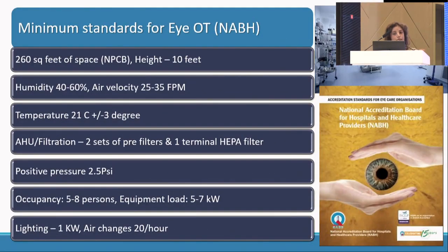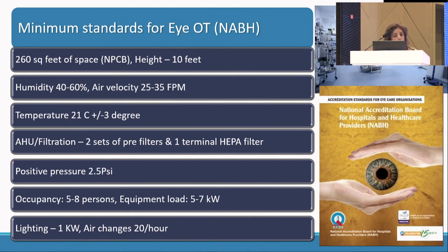The minimum standards as recommended by NABH include an OT size of 260 square feet, but AIOS has reduced this — it can be 160 square feet provided the number of persons inside the OR is limited to four. Humidity needs to be maintained at 40 to 60%, temperature at 21 ± 3 degrees. An air handling unit with positive pressure should be maintained if possible. Occupancy should preferably be kept to four or below, and lighting should be 1 kilowatt.